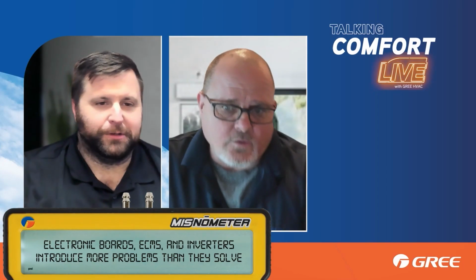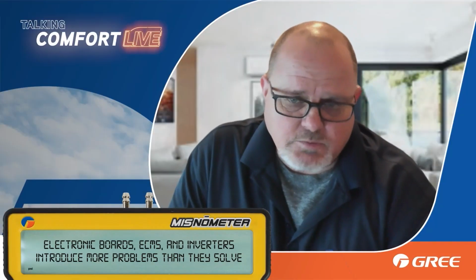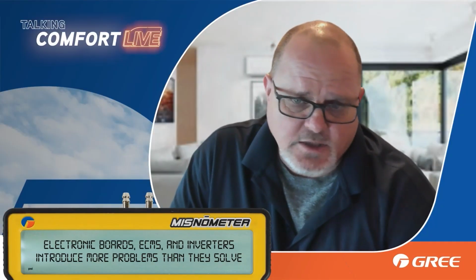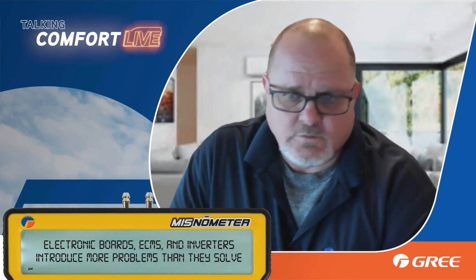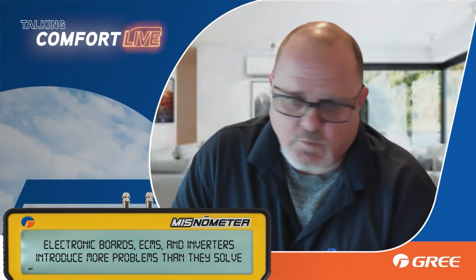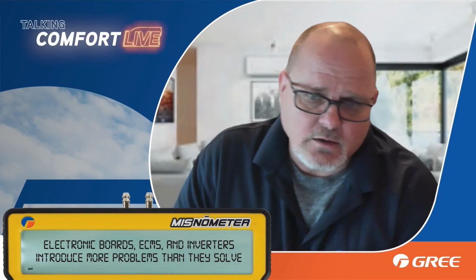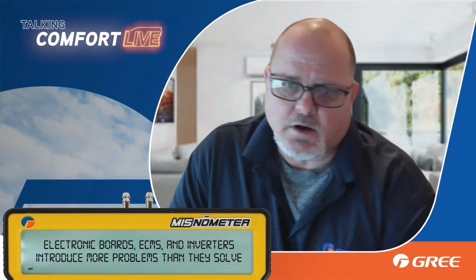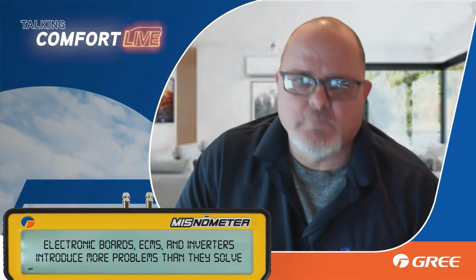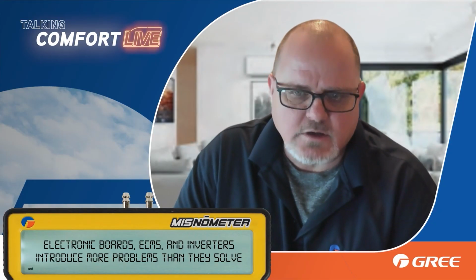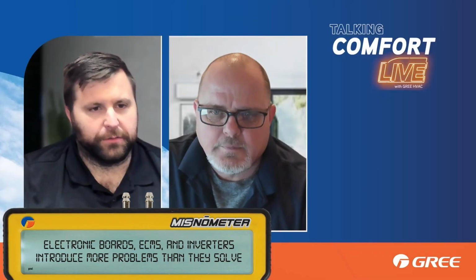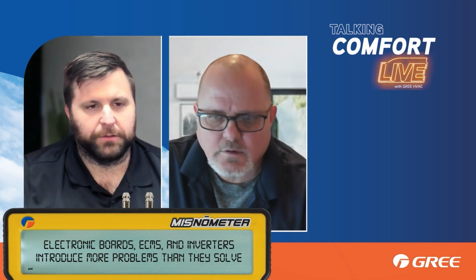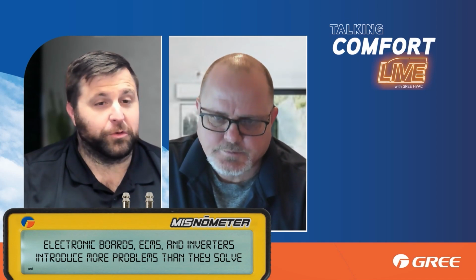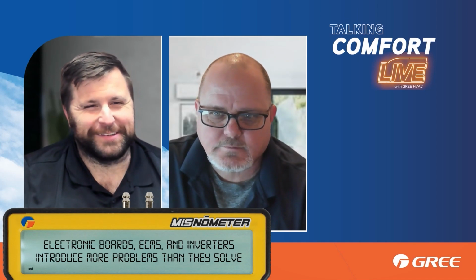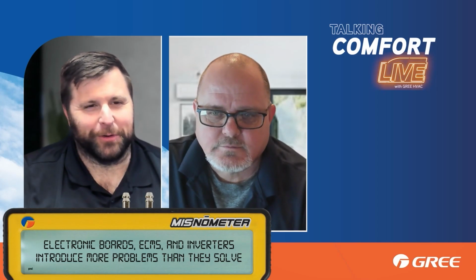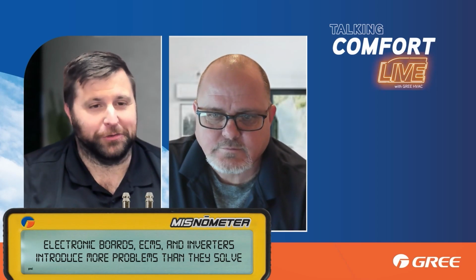But you're right, those motors are driven in many different ways. They use pulse width modulation. That's no different than what we have in our equipment, where you have a 5-wire fan motor or a 3-wire fan motor. How that motor is communicated to come on is a little different. It could be a 0 to 10 VDC signal, which is really cool, because years ago on a 0 to 10 blower motor, I used a 9-volt battery to give it a signal.